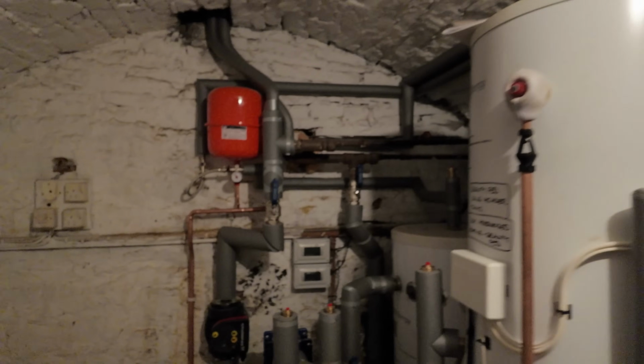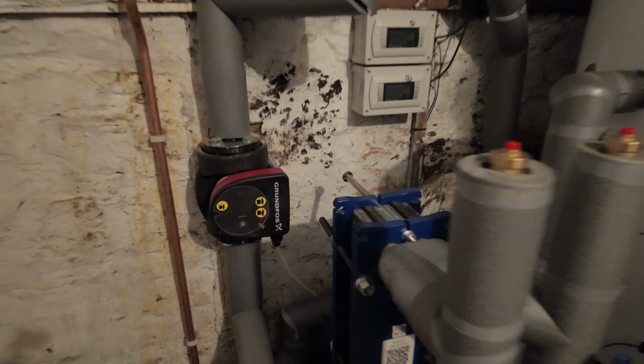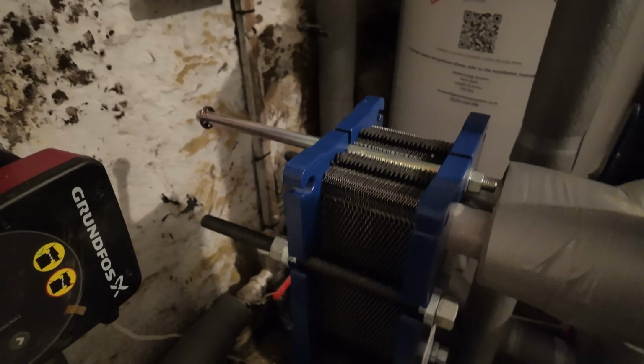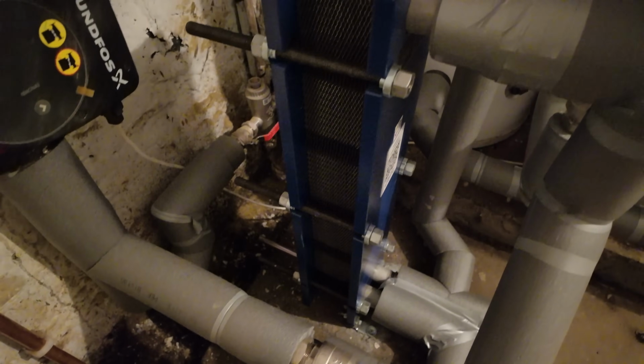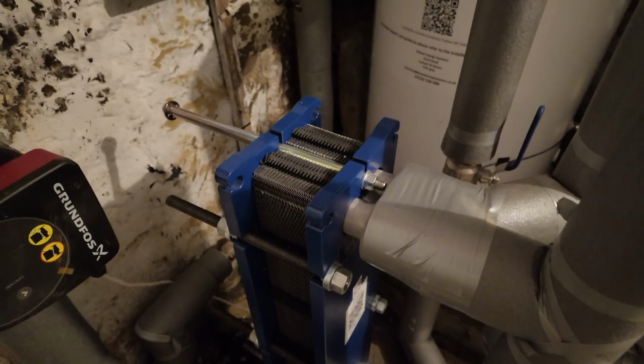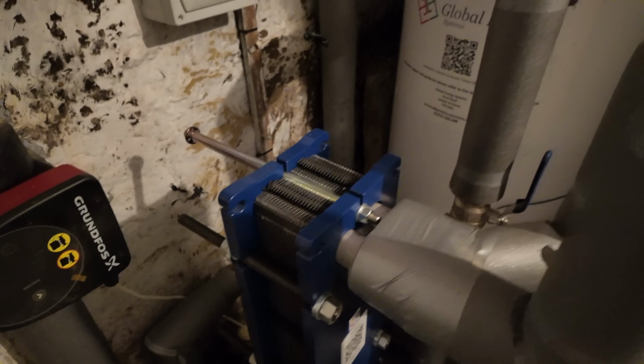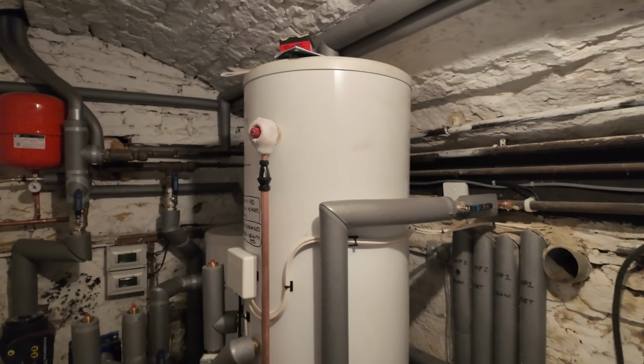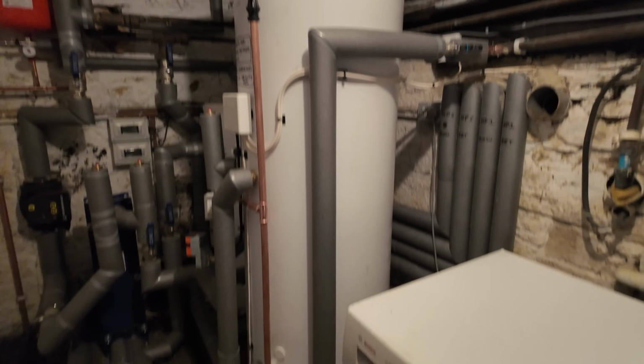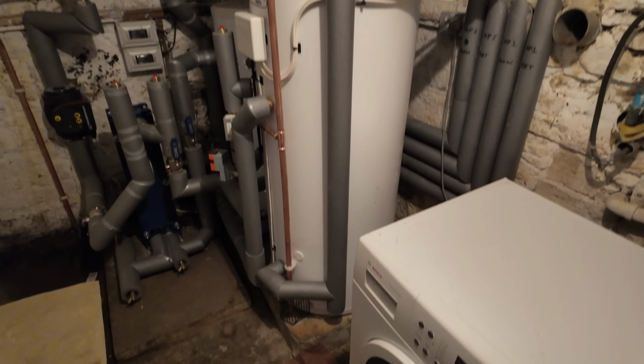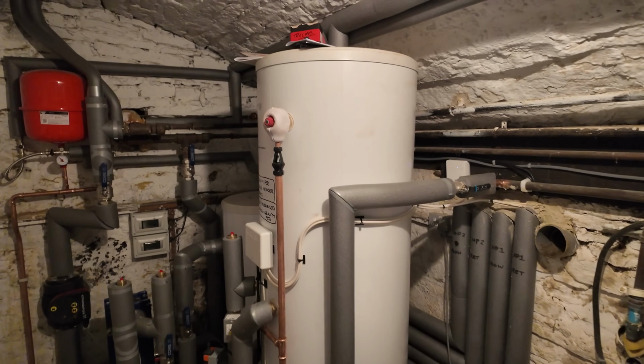I'll just show you it. It's not got its insulation jacket on at the minute, but that is the heat exchanger. Now it's huge. A lot of engineers that are used to installing heat exchangers on high temperature applications might think, crikey, 26 kilowatts, that's massive, and it is, but we've done it for those reasons, okay? So that's that. We have got a 500 litre hot water tank because of the size of the house and the amount of occupants that can be in here.